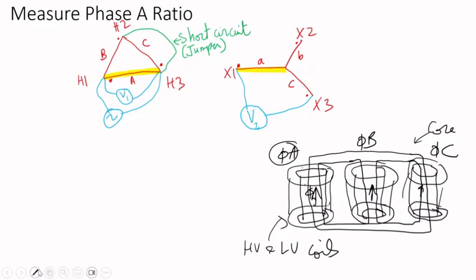Then B phase, so I'm showing B phase here. Then I'm going to find the parallel, which is this one. So those are parallel, that means they're wound around the same core leg. Then find another. Then phase C, so if I highlight phase C here, then I'm going to find the one that's parallel to it on the low voltage. They're color coded. Each parallel pair means they are wound around the same core leg.